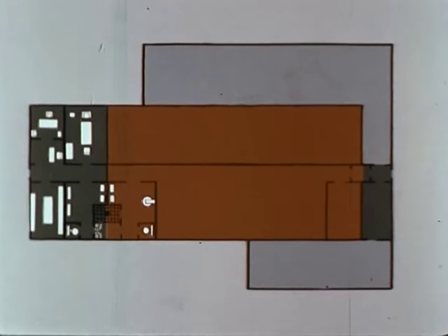In the rear of the facility is also a clean area with a transitional airlock. This serves to handle the inward flow of laboratory supplies into the building and the outward flow of materials from the building. Supplies entering the infectious areas are passed in through the UV airlock. Potentially infectious material leaving the building is treated in a double-doored steam or ethylene oxide sterilizer.